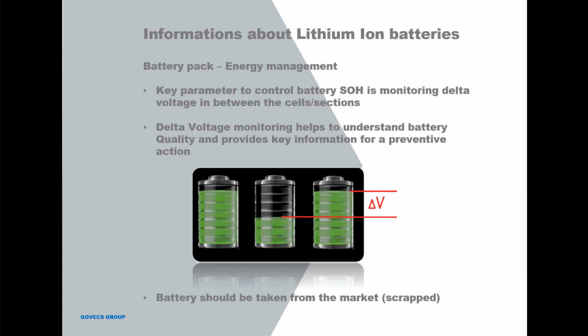The key parameter to control the battery state of health is to monitor the delta voltage between one cell or section and another. This information gives us an impression of how good the battery is, and in any case it tells us if we should take action, or in the worst case, withdraw the battery from the market.